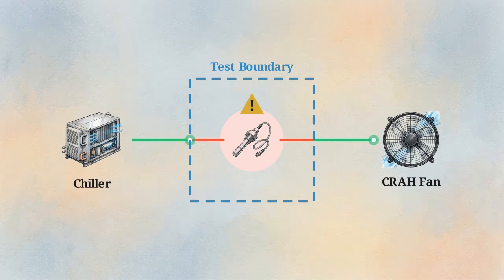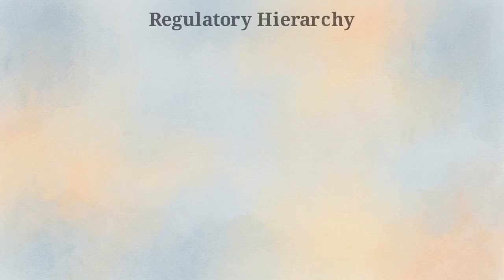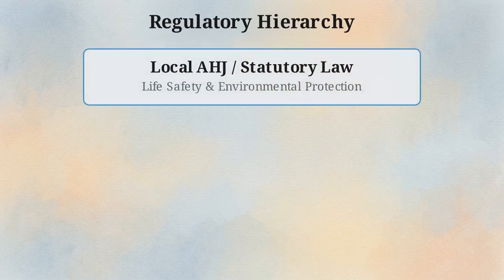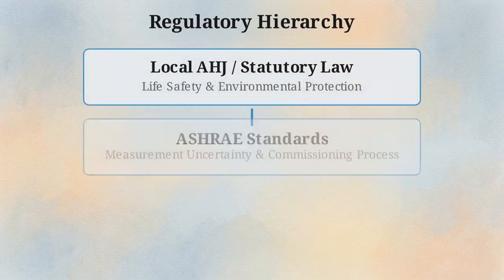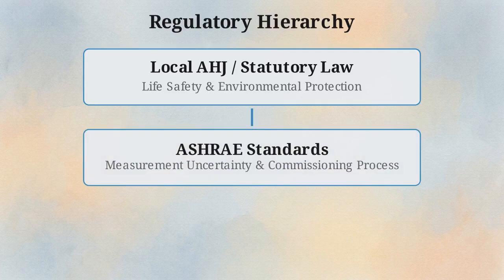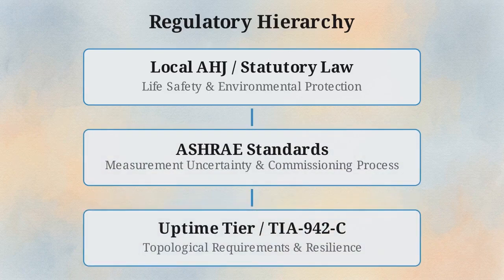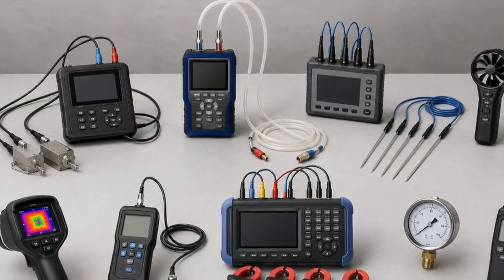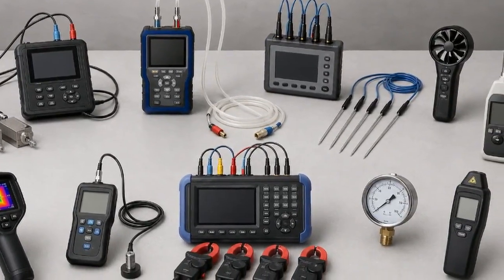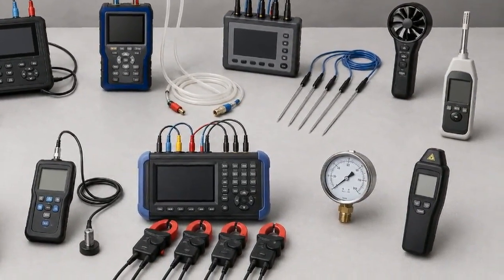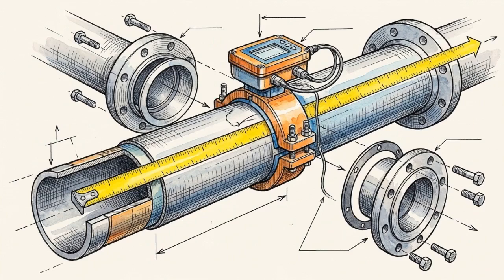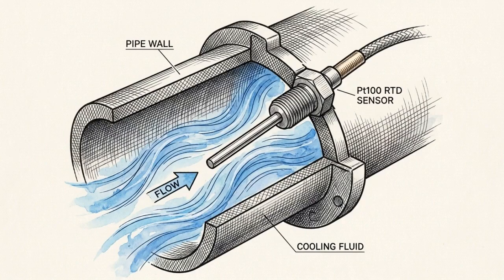The pass and fail values for these tests are dictated by a strict regulatory hierarchy. Local authorities having jurisdiction control life safety. ASHRAE dictates exact measurement uncertainty, and Uptime or TIA 942C governs the topological requirements. But a valid calibration certificate is entirely useless if the physical placement of the instrument is flawed. We rely on precise physical instrumentation.